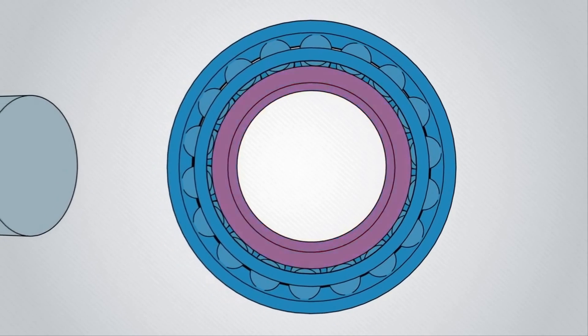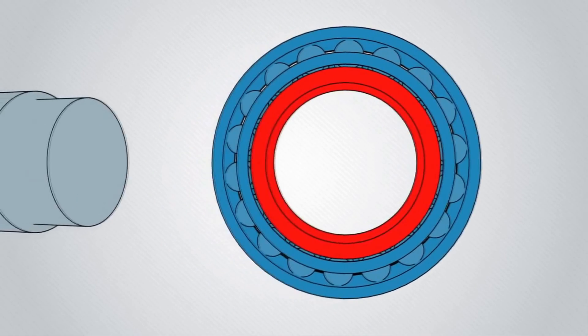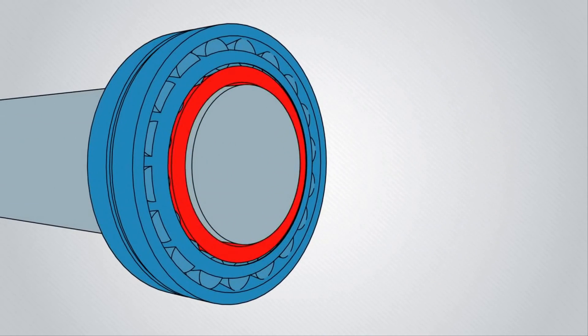This is why heat is used to expand the bearing inner ring before placing on the shaft. As the bearing cools, a stronger interference fit results.